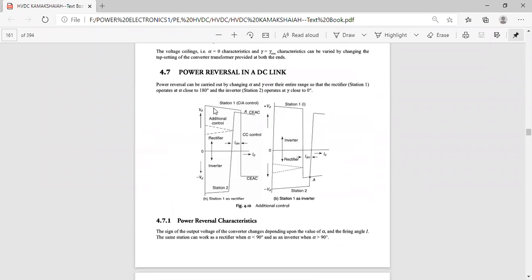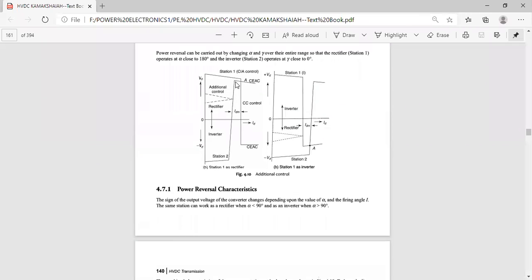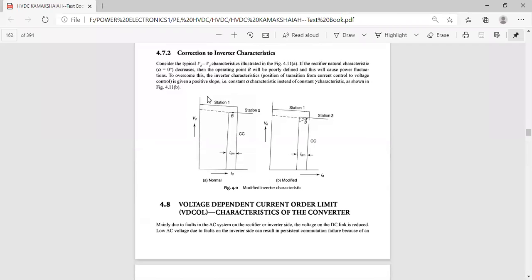In the power reversal case, this is the characteristic of the rectifier and this is the characteristic of the inverter. For the inverter characteristic, a correction has been done. Instead of a flat characteristic, we have given a positive slope to the inverter characteristic.